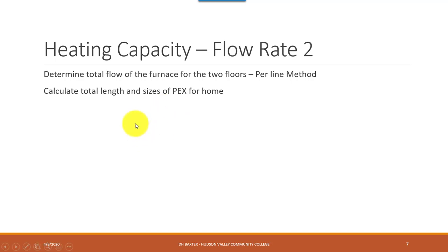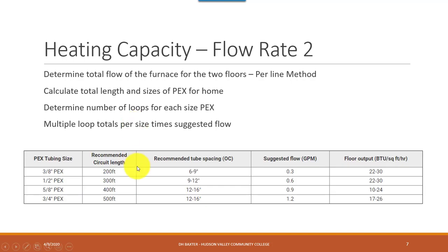The other trick is the per-loop method. You calculate the total length and sizes of the PEX for the home — say you're using half-inch for almost all of it — and you determine the total number of loops, then multiply by 0.6 GPM. It'll come out close, maybe a little higher or lower. This is a more accurate approach but takes longer, and it'll be close to the bulk method. The bulk method gets you in the ballpark quickly; this fine-tunes that answer.